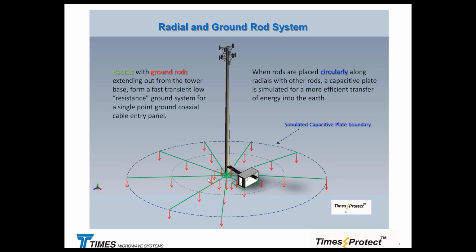So if it was up to me, I would rather take three radials or four radials, whatever the real estate will allow, and run them and then go with the grounding rods from each one of them. Don't make the radials too long, because even though they're going to be buried in somewhat conductive soil, they will be subject to impedance as well. And there is going to be some point of diminishing energy which won't be able to overcome the length of the radial. So the best way to ground the tower, and that's the first place I advise people to start, is to create a system of radials and grounding rods, basically, to take the step potential rise as the current keeps coming down away from the shelter.